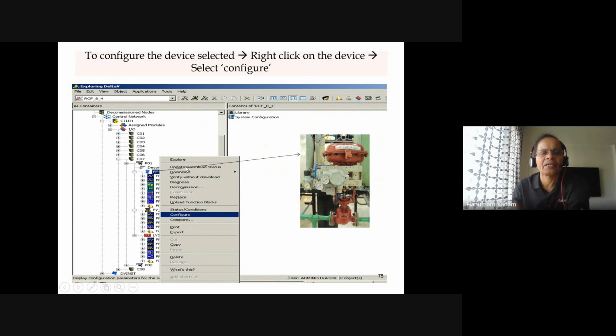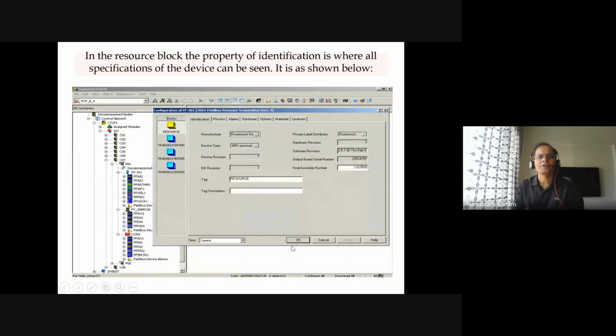You will get a window to configure. In the pop-up window, you can just click on configure. The moment you configure, in the resource block there are three transducer blocks. So in the resource block this information is available: tag name, tag description, the make is automatically coming, Rosemount and this. So you only have to insert a tag description here and say okay.